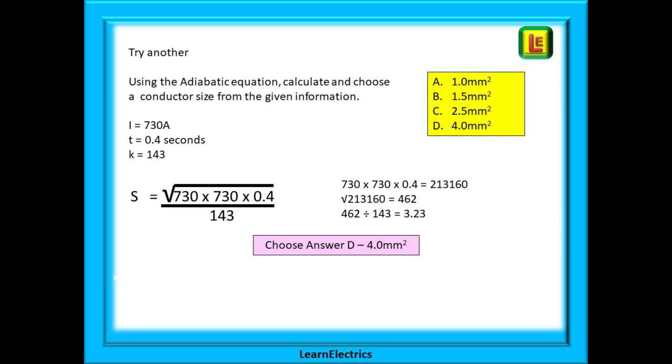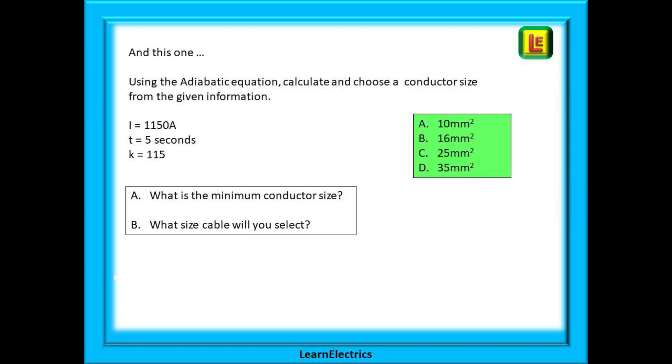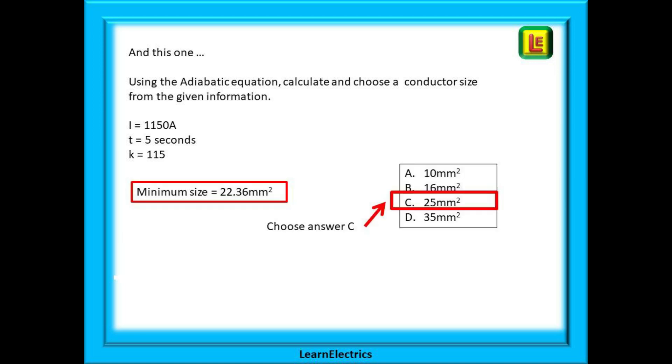And not just for the exam, this is what you would choose on site in the real world. Now do this one using the information that is provided. Pause the video whilst you do the calculation. And you should have a minimum size of 22.36 millimeters making you select Answer C, the 25 millimeter conductor.